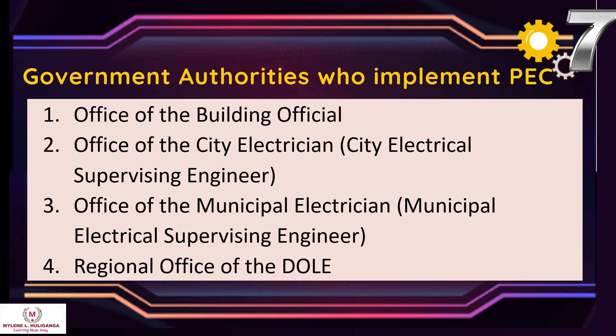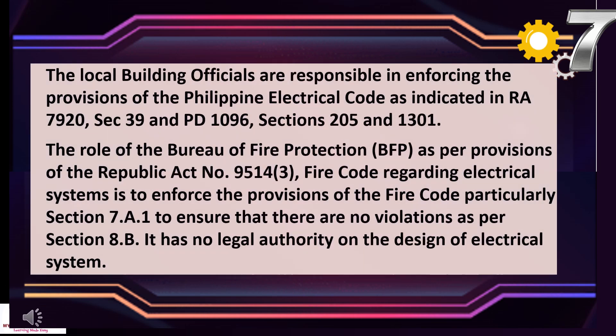The government authorities who implement the PEC are: (1) Office of the Building Official, (2) Office of the City Electrician/City Electrical Supervising Engineer, (3) Office of the Municipal Electrician/Municipal Electrical Supervising Engineer, and (4) Regional Office of the DOLE. The local building officials are responsible for enforcing the provisions of the PEC as indicated in RA 7920 Section 39 and PD 1096 Sections 205 and 1301. The Bureau of Fire Protection (BFP), as per Republic Act No. 9514 Fire Code, enforces fire code provisions particularly Section 7.a.1 and Section 8.b, but has no legal authority on the design of electrical systems.